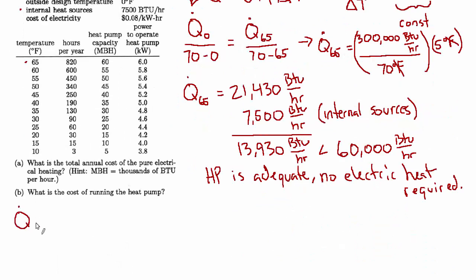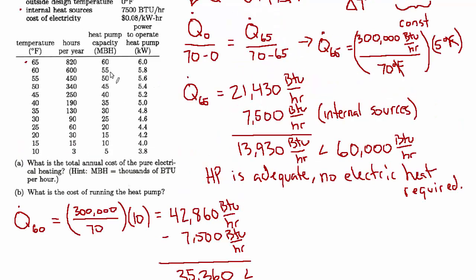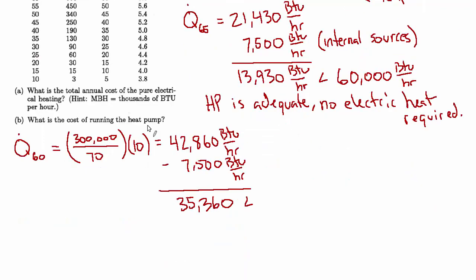We have 7500 BTUs per hour of internal heat sources. So we'll subtract that since we're getting that for free. That's heat that's going on inside regardless. And that difference then is 13,930. And now we'll notice that the capacity of the heat pump at that outside temperature is 60,000 BTUs per hour, which is far greater than 13,930. So the heat that we need is much less than the capacity of the heat pump. So we don't need to run the electric heat. The heat pump is adequate by itself.